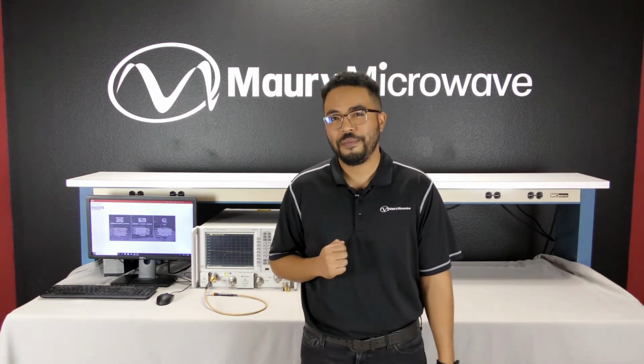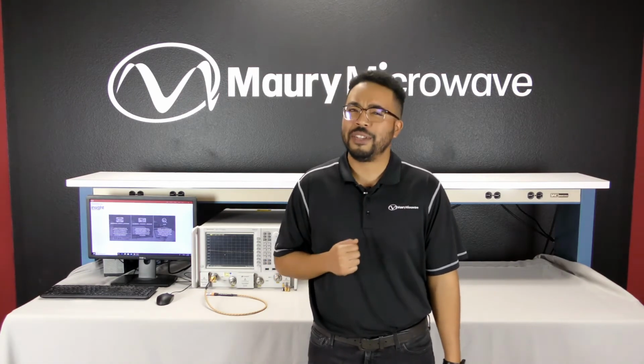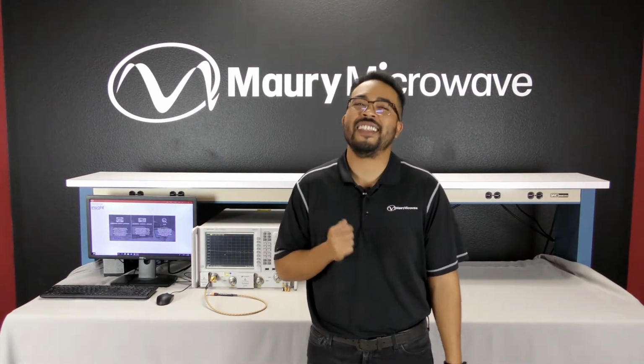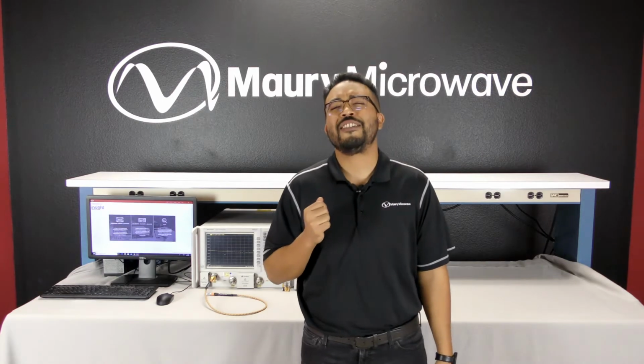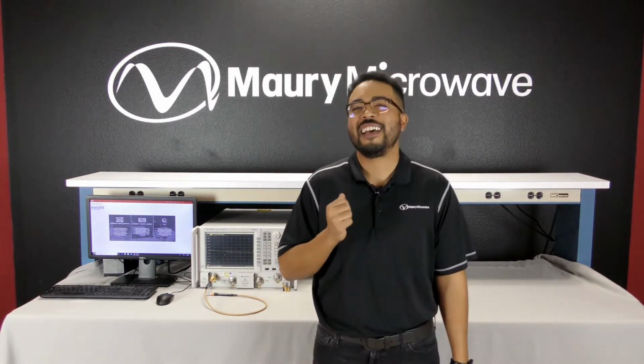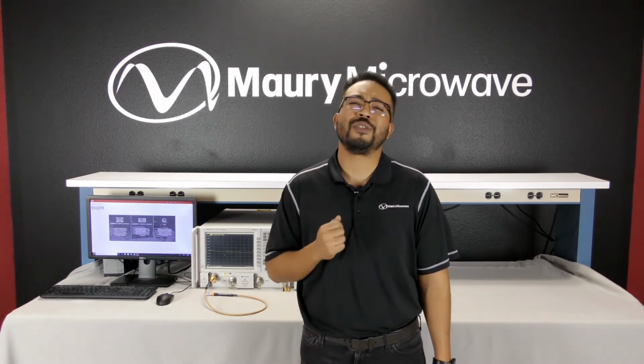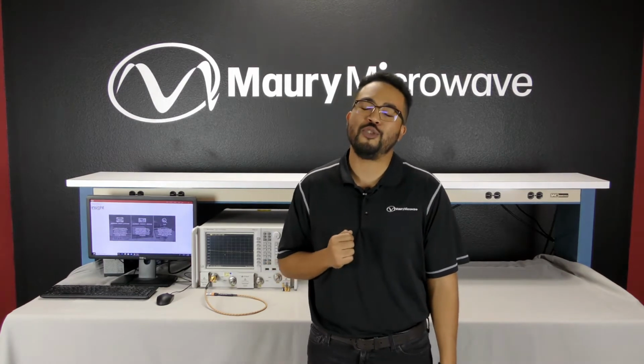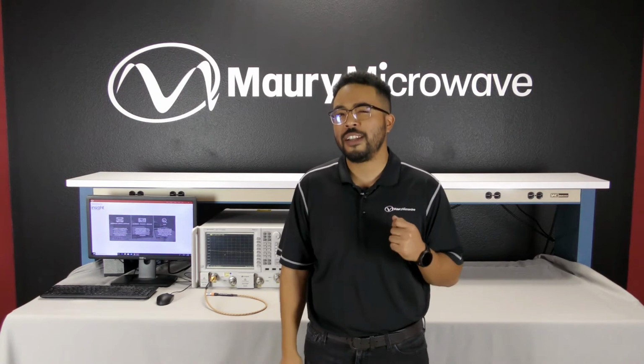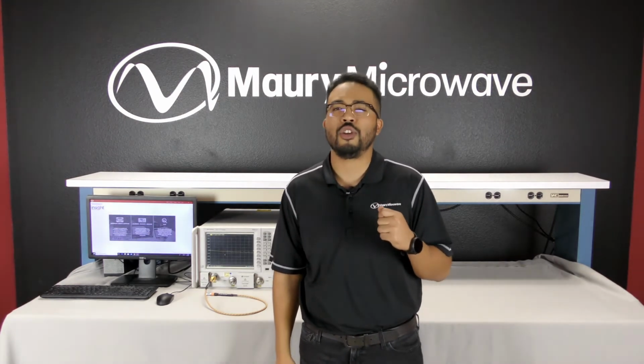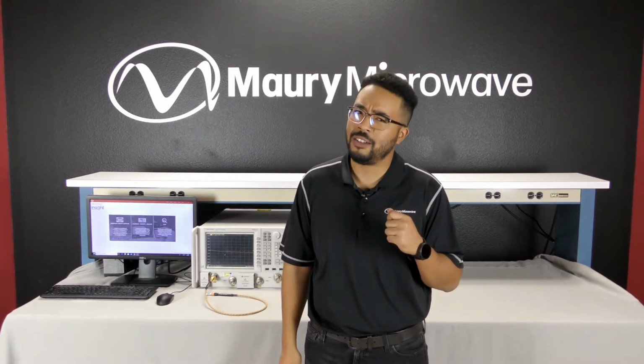Doesn't sound familiar? Well, let me explain. Cable isn't binary. It doesn't work one day and then stops working the next day. Its degradation is slow. At some point, its performance changes ever so slightly and adds a little error to your measurements. It may be negligible at first, but as the cable continues to degrade, the errors get larger and larger until one day you realize that something doesn't look right.